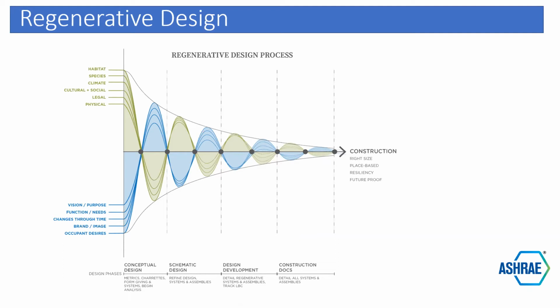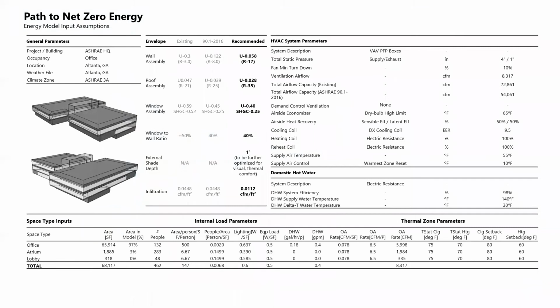With a construction design that we believe is right-sized, and it's going to meet our needs well into the future. Path to net zero, and I'm not going to talk about all this on here, but what's key is the area that talks about the recommendations. So wall assembly, we're looking at R17 minimum, roof assembly R35, window assembly U.4, and window-to-wall ratio target of 40%. External shading, having 1 foot external shading in key areas, and an infiltration level of 0.0112 CFM per square foot. These were some key parameters for us in terms of getting our energy use down.